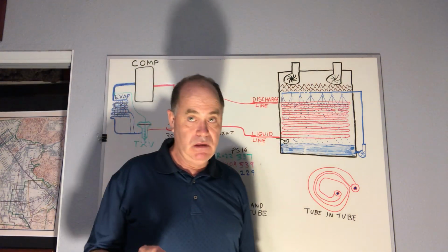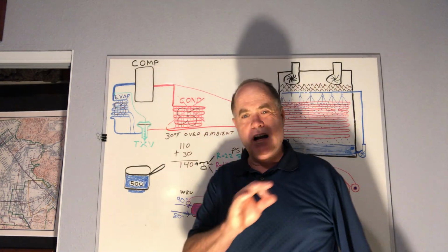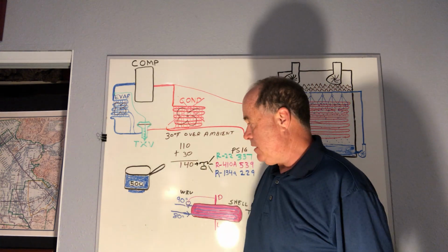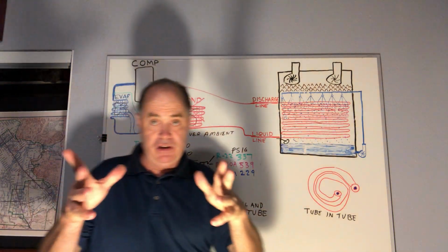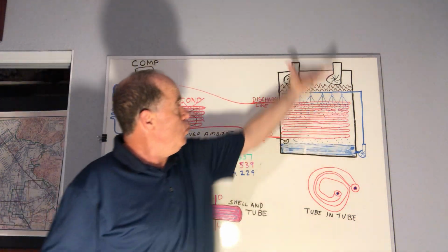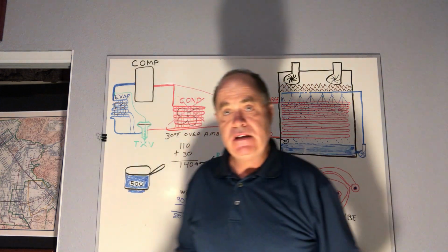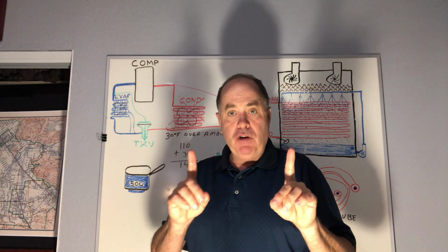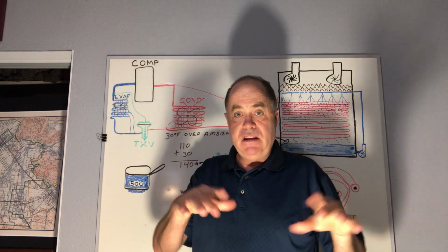Now, let me finish the presentation, just talk a little bit. I could go for an hour or more easy on water treatment. With the evaporative condenser and also with cooling towers, you're getting water that's evaporating. And it's the pure water that evaporates and the minerals stay behind.